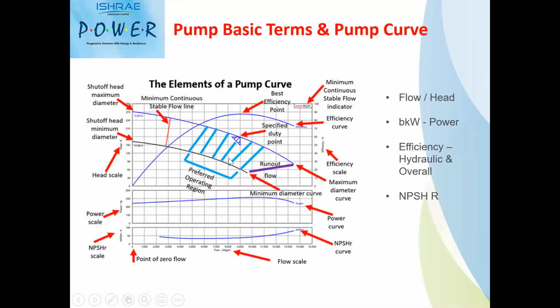And then we have the preferred area of operation, because pumps will typically have efficiency. This is the best efficiency, as I told. The efficiency keeps on dropping as you move towards the right hand side of the curve. Efficiency keeps on dropping as you move towards the left hand side of the curve as well. So this is the best efficiency point, this one. Efficiency keeps on dropping on the left hand side of the BEP as well as the right hand side of the BEP.